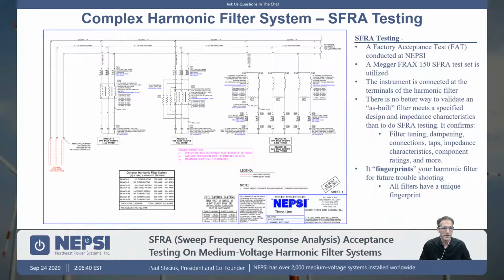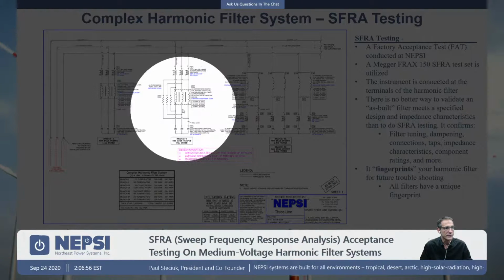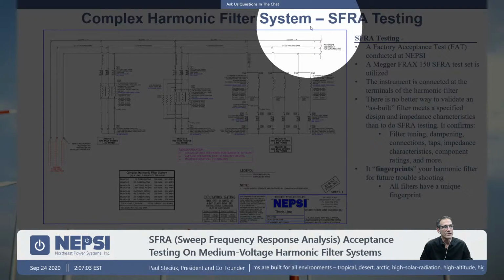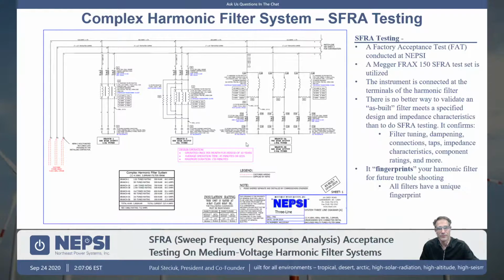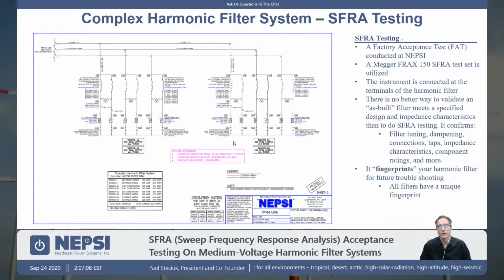So up on the screen here, I show a very complex harmonic filter system. This particular harmonic filter was used for a black start project. You can see here that we have a standard notch branch, a high pass branch, and then what I would think is classified as an H filter. But the system continues on through to another bus bar where we have more complex filters. So a very, very complex harmonic filter system.